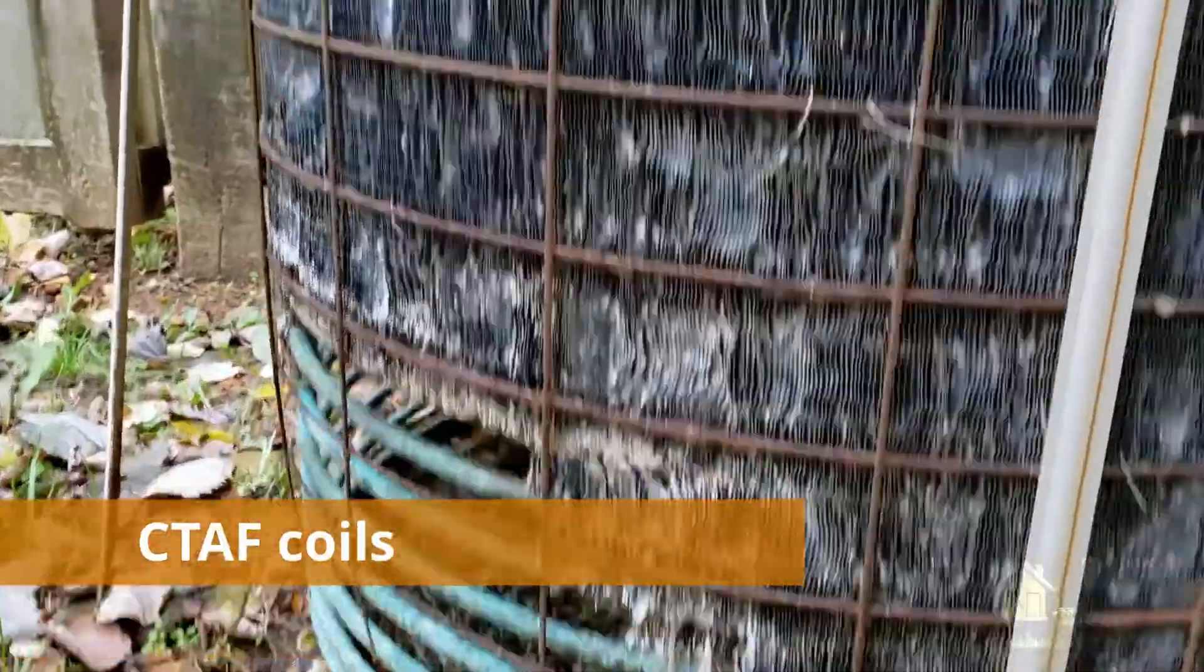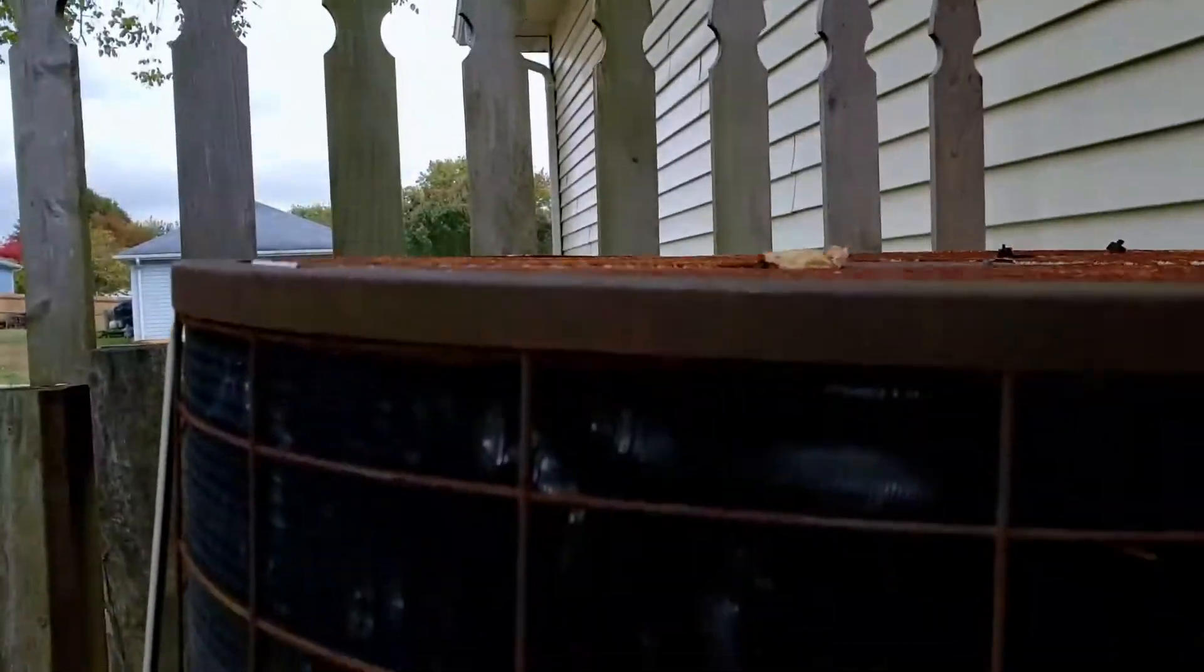The green coils, that's the copper. That's the refrigerant. The outside that's dissolved, that's aluminum. The urea in the pet urine dissolves the aluminum. The aluminum acts like a heat sink.